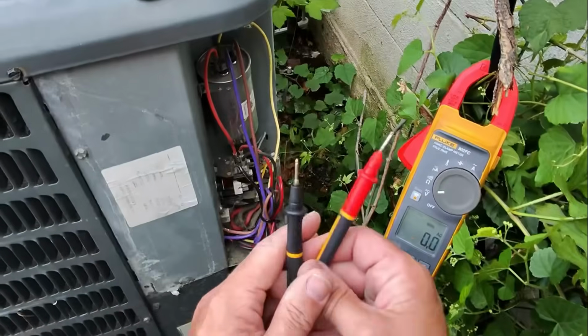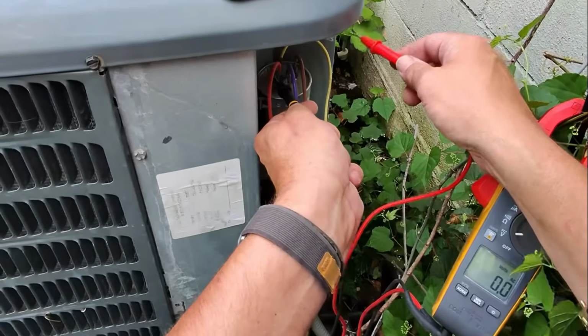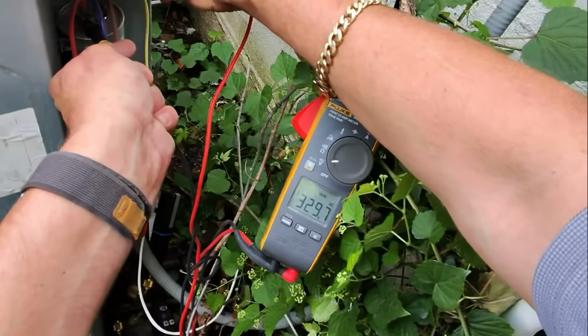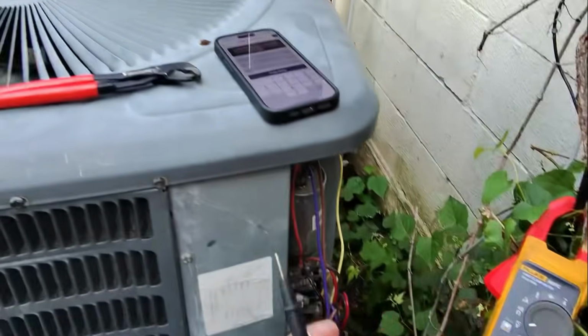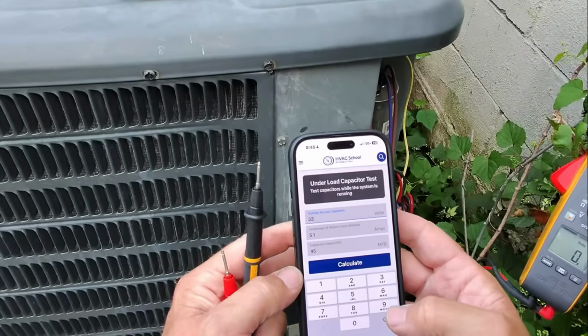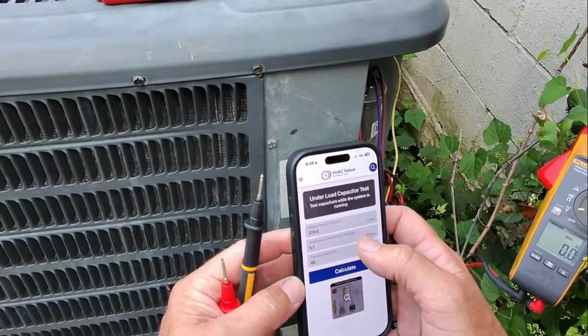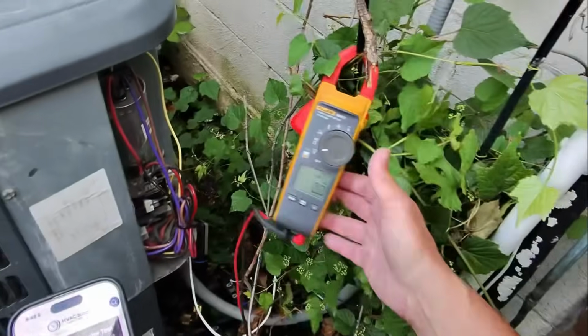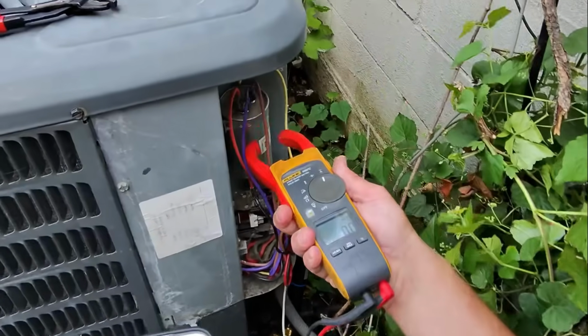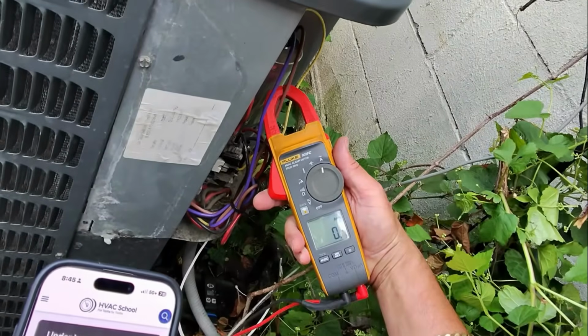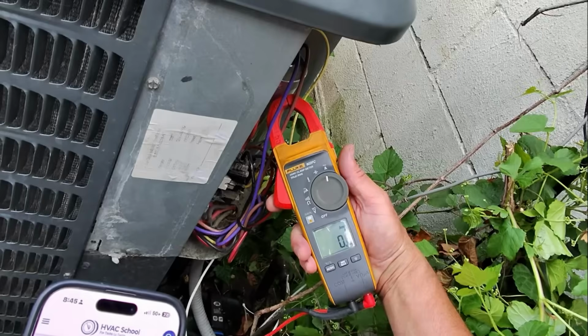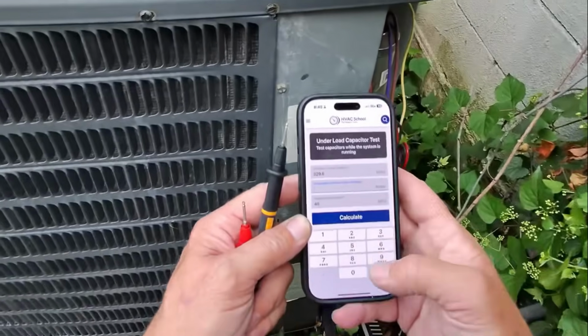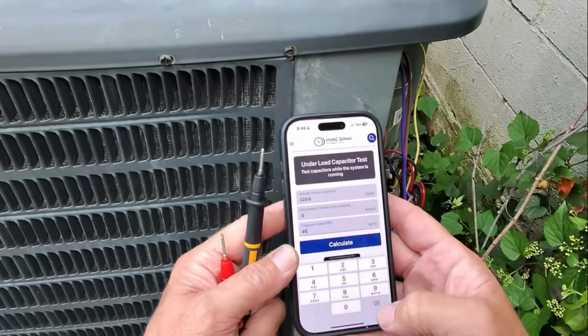Let's get a voltage of that between common and there. We are getting 329.6. Let's get an amperage reading on that brown wire. We're getting 0.6, and this should be a 5. All right, so the two capacitors are within range.